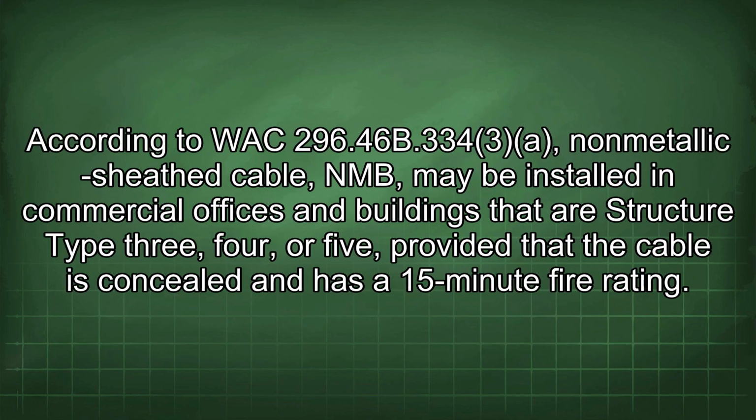According to WAC 296-46B-334, non-metallic sheathed cable, NMB, may be installed in commercial offices and buildings that are structure type 3, 4, or 5, provided that the cable is concealed and has a 15-minute fire rating.